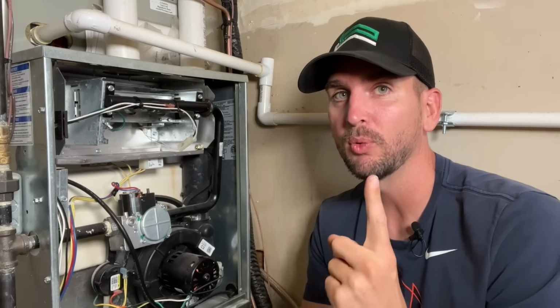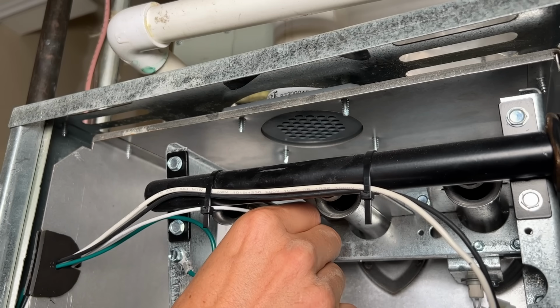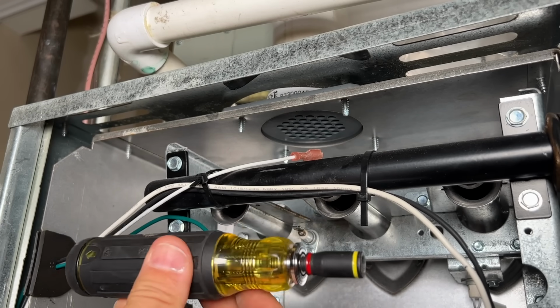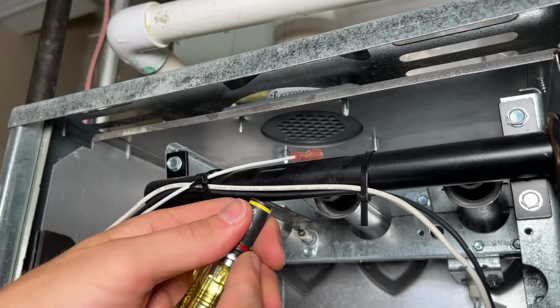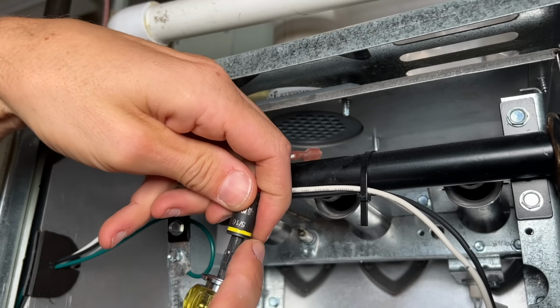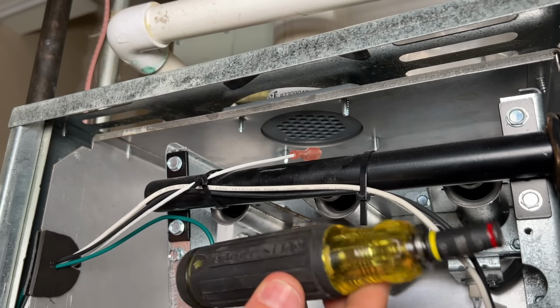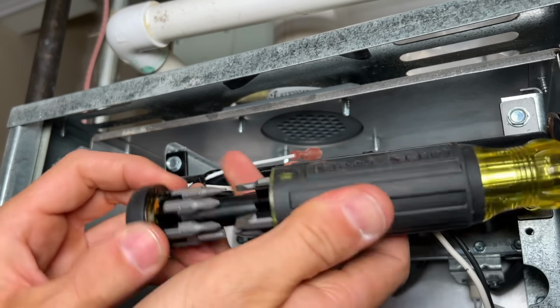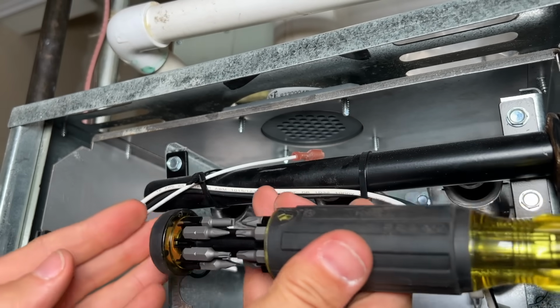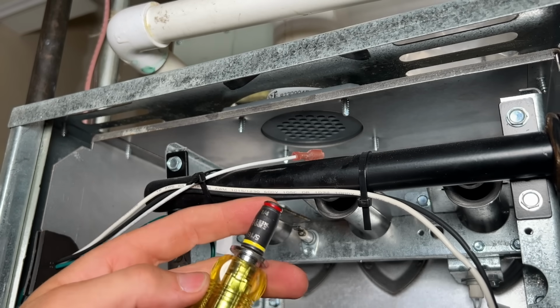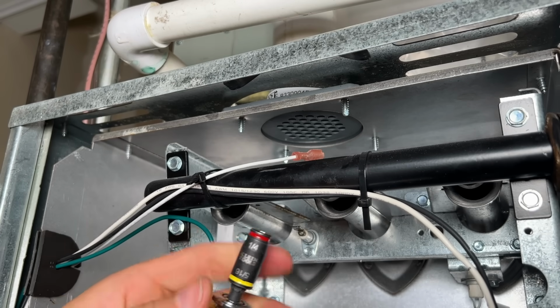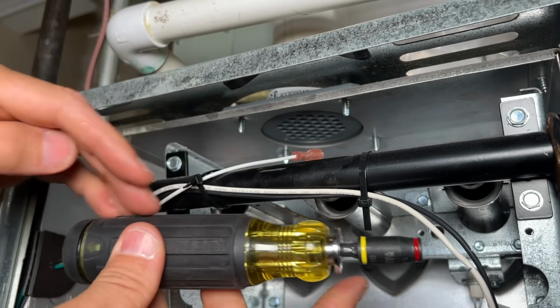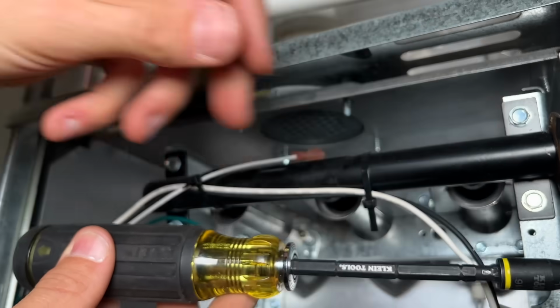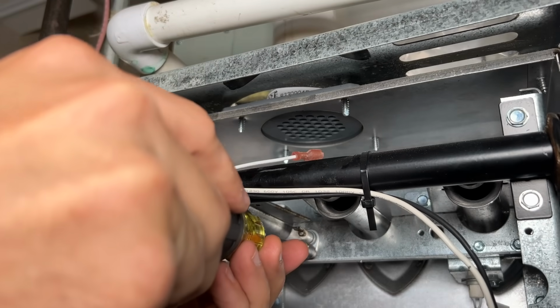And also, again, remember, one of my issues, I didn't need any parts because a simple cleaning can sometimes solve this issue. So removal is super simple. We'll take the connector off the spade terminal, and then with that same Klein Tools 14-in-1, I'm gonna flip it from the 5/16 I needed earlier over to the 1/4 inch. This screwdriver is awesome for HVAC work because you also have all your different bits in the base, which will fit into the 1/4 inch nut driver, which also serves as a bit holder if you just move it out a little bit further. And then you can make it compact or extend out that shaft to reach things like this flame detection sensor.